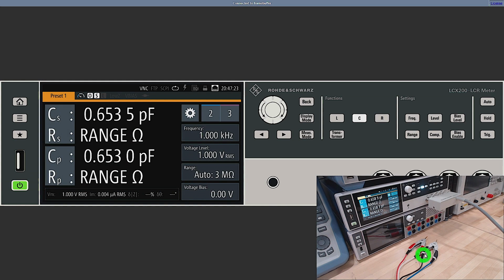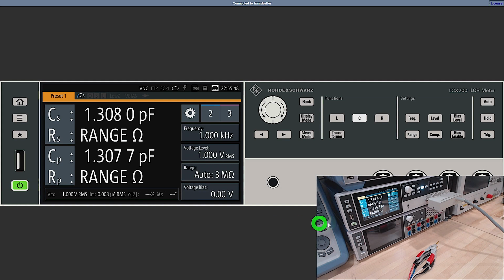Now right now, as you can see here at the bottom, there's nothing connected to those Kelvin clips, so we're basically measuring this open capacitance. And the reason we're seeing it is because I have not calibrated the unit to get rid of it. So here now I have moved the probes on top of each other so that they're roughly at the same distance they would be when I want to measure my device. Now the coupling capacitance between them right now is 1.3 picofarad, and we want to get rid of this. Before we do this, let's make sure the settings are where we want them to be.